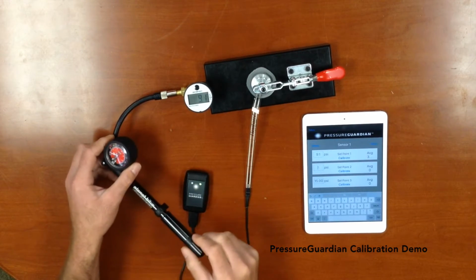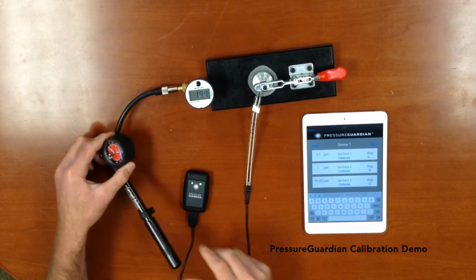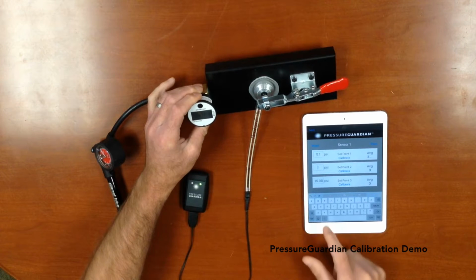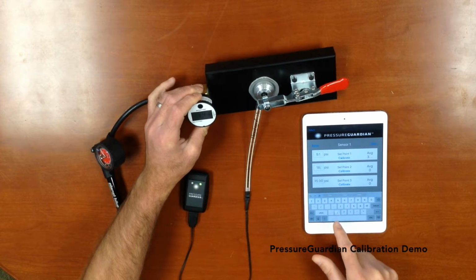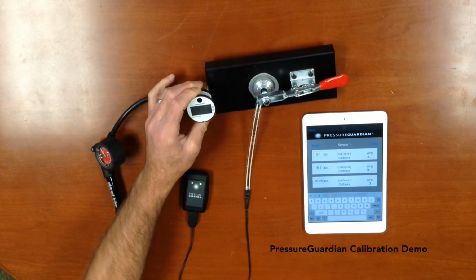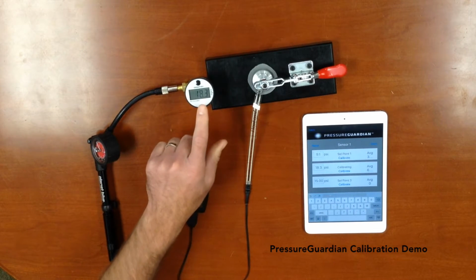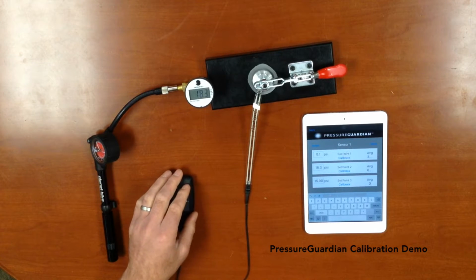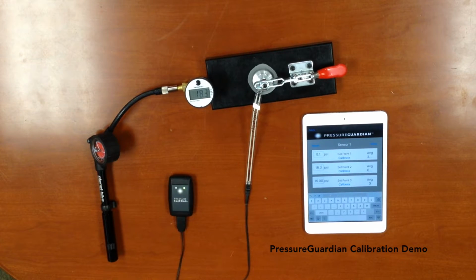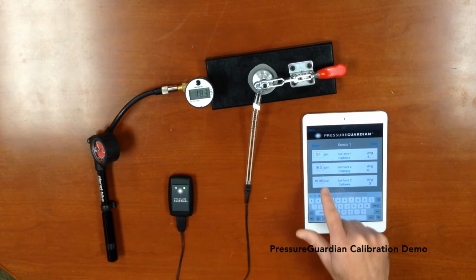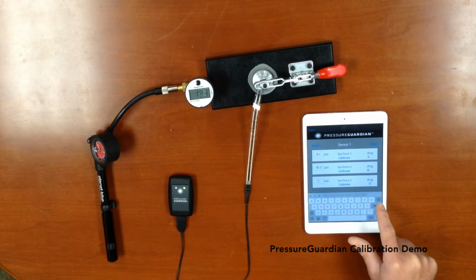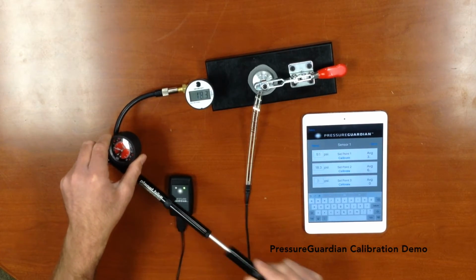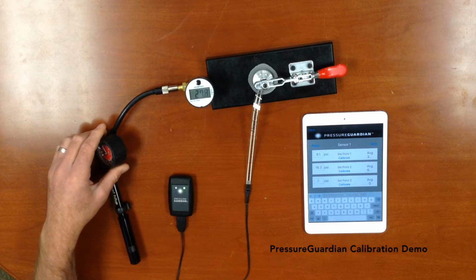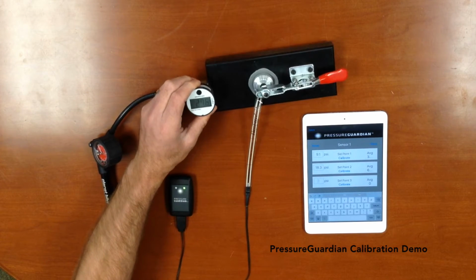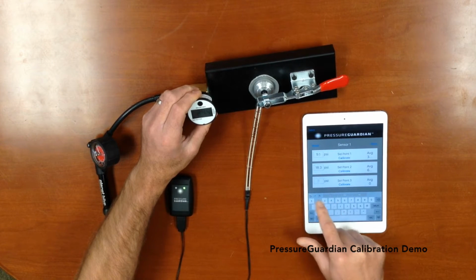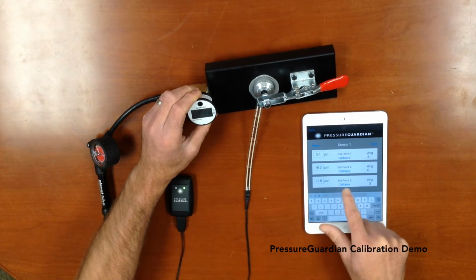I'm going to give another full revolution, read my number, which is 18.3. We're going to hit calibrate. And it's good to let the gauge plateau out. Initially it may drop 1 to 2 psi. Now we're going to go into our third and final set point. 1 full pump. And then we're going to give it a couple seconds to stabilize before typing in our final number.